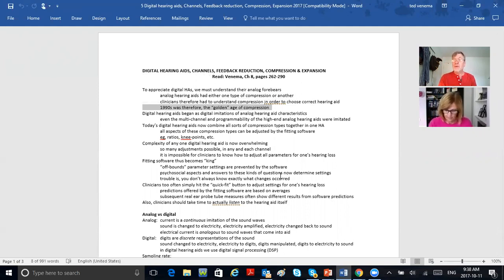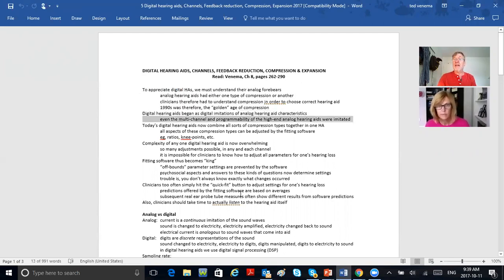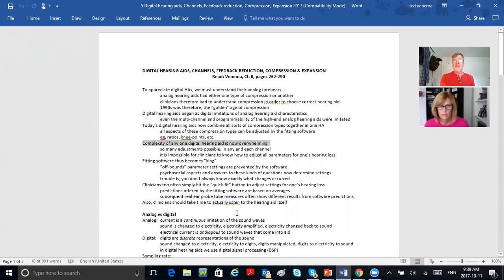That's why the 90s was the golden age of compression. Today we don't understand compression quite as well because the digital software does it all for us. Digital hearing aids began as digital imitations of their previous analog hearing aids, even imitating the multi-channel and programmability of high-end analog hearing aids. Today's digital hearing aids combine all sorts of compression types together, and all aspects can be adjusted by the fitting software — knee points, ratios. The complexity of any one digital hearing aid today is now overwhelming, and that's why you need the software.